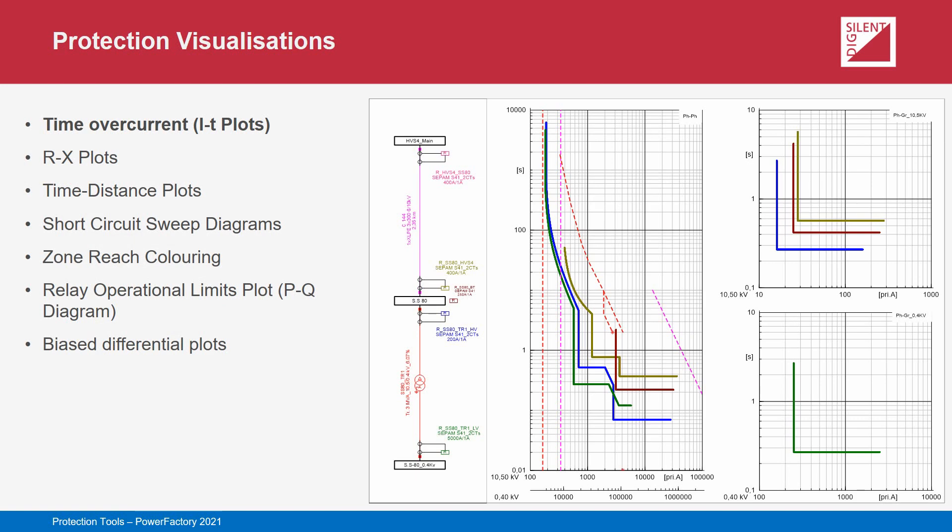Various plots are available within the software for visualization of settings and results. Some are highly specific to protection functionality and are well known to protection engineers. All plots are interactive, and relay settings can easily be modified through those interactions. Time overcurrent plots are used with overcurrent protection, representing the tripping characteristics of coordinated relays on a logarithmic current-time axis. These plots can also display cable damage curves, transformer damage curves, inrush characteristics, motor starting characteristics, and current constants illustrating fault or loading condition magnitudes.